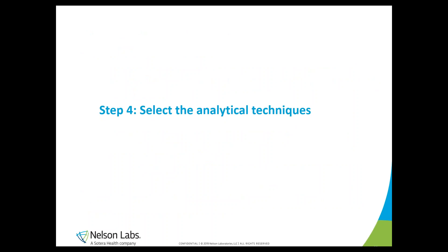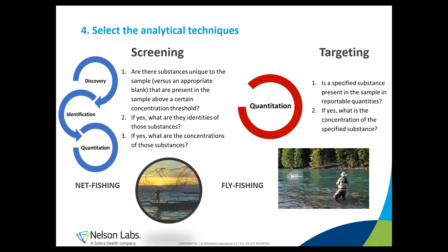The different analytical techniques to be used in an extractable study will also be described. Why would one single analytical technique not be enough? It's important to know the difference between a screening approach and a targeting approach. In a screening approach, you screen for every potential compound in your extract by comparing the profile of your medical device extract with a blank, reporting, identifying, and quantifying every compound differentially present in the extract of your device that is not present in the blank.